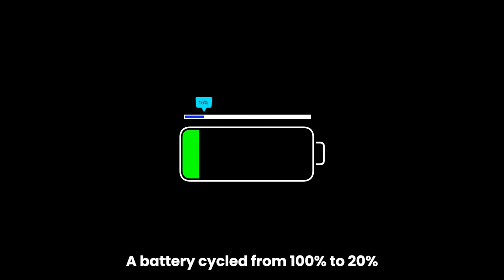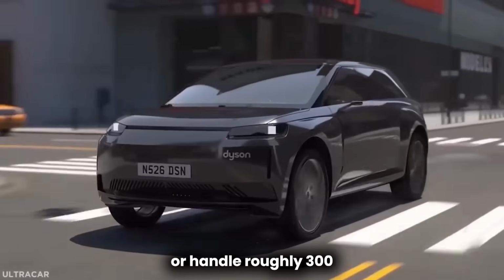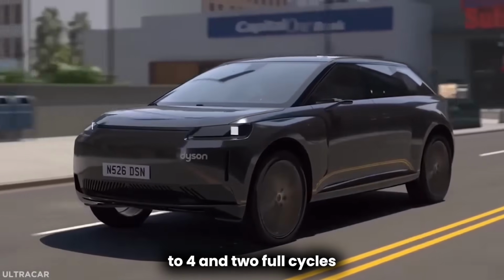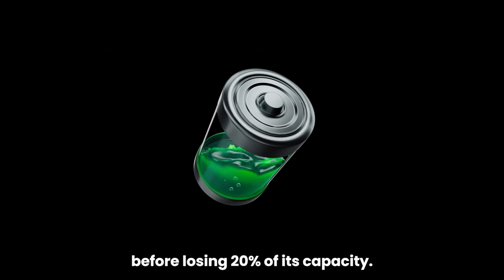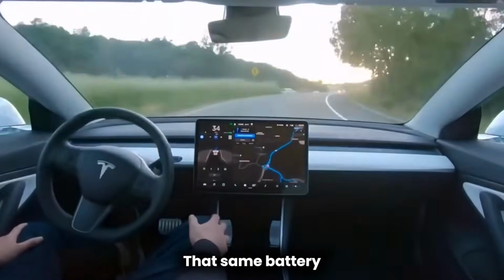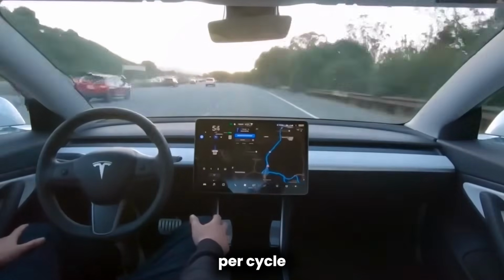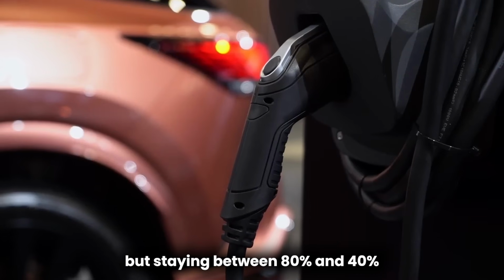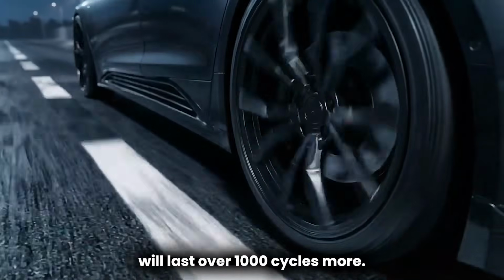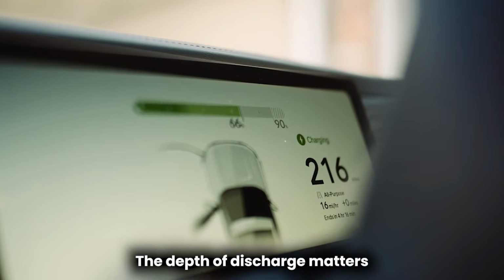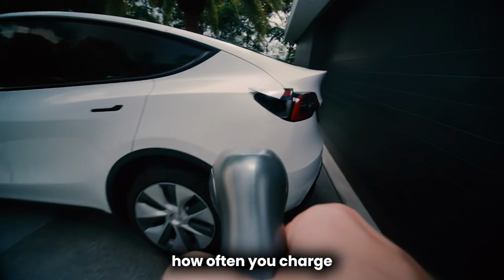A battery cycled from 100% to 20% will handle roughly 300 to 400 full cycles before losing 20% of its capacity. That same battery, using the same amount of energy per cycle, but staying between 80% and 40%, will last over 1,000 cycles more. The depth of discharge matters more than how often you charge.